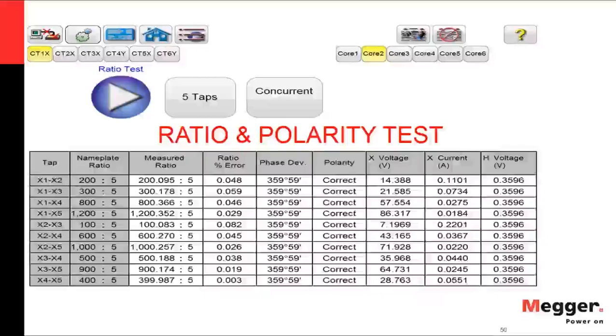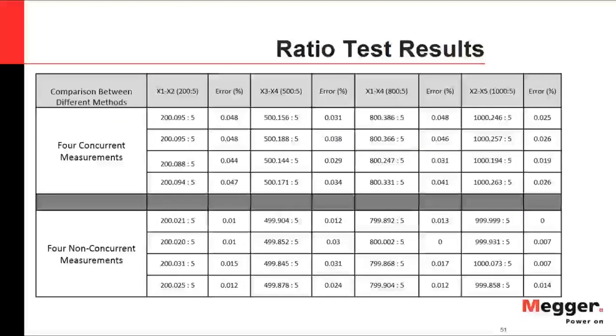For ratio and polarity tests, the ratio magnitude and phase deviation are calculated. Phase deviation should be zero degrees or very close to zero — 359 degrees 59 minutes is acceptable. Polarity is verified as correct. Comparative analysis between concurrent and non-concurrent ratio and polarity measurements again shows negligible differences.